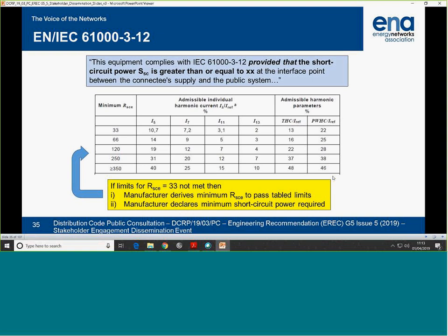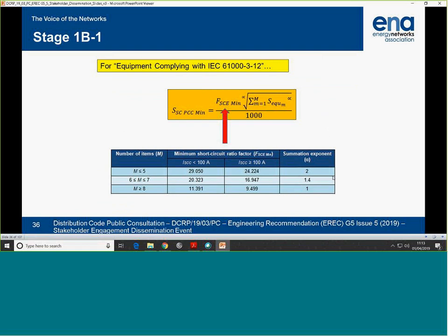So with this information, use this for the design. So if I show how we do that. For complying with 312, that's the simplest case. I have a formula. On the right is S_EQU with a subscript of M. The first item M is 1, second item M is 2, and so on. So it's the rating of the equipment, basically. This alpha exponent, which is a summation exponent, has its basis in what Farouz went through earlier, and I'll explain why they are around it in the table below in a minute. But taking the ratings, you're summing them, and then you're rooting them, and then you're multiplying by a factor.